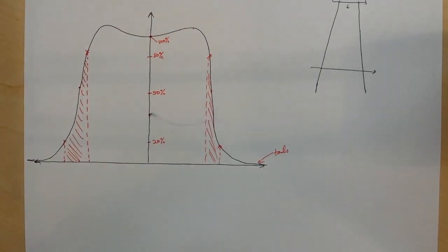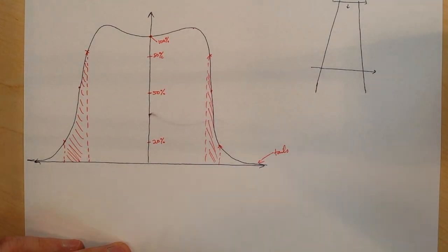Most manufacturers are going to specify the penumbra as the 20% to 80% line. In Khan, you'll read it that it's either 20 to 80 or 90 to 10, but most people use 20 to 80 because it's a smaller width than 90 to 10, and it makes your machine seem like it has a tighter beam. So when you talk about the tightness of the beam, the tightness of the beam is how small is the penumbra, because the penumbra represents the fuzziness of the beam, the fuzzy edge of the beam.